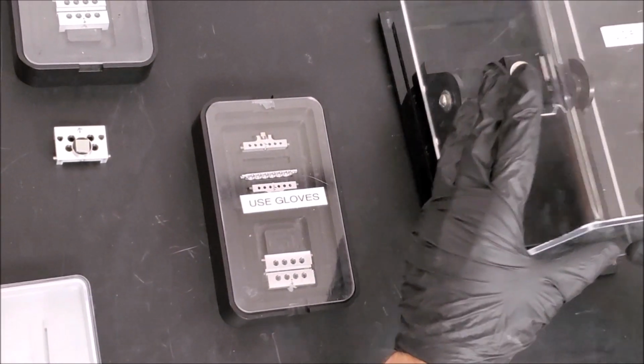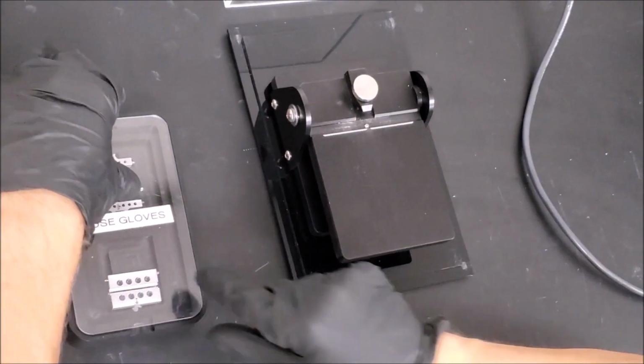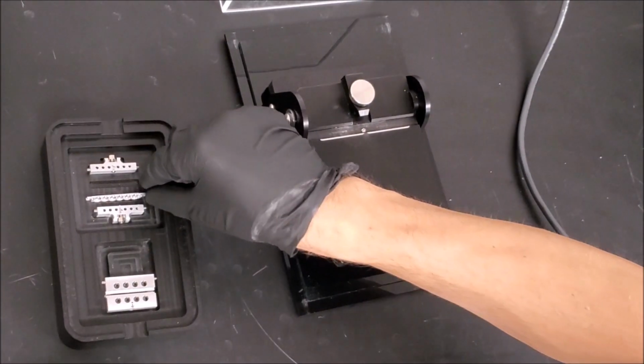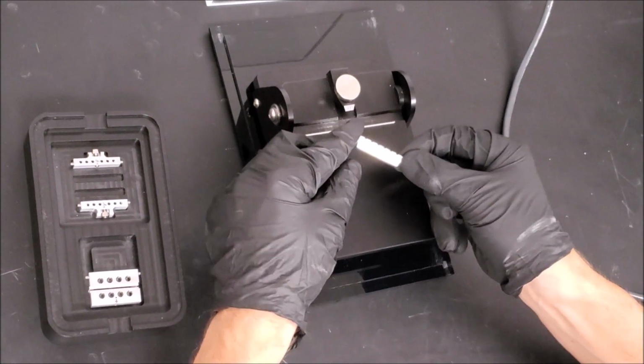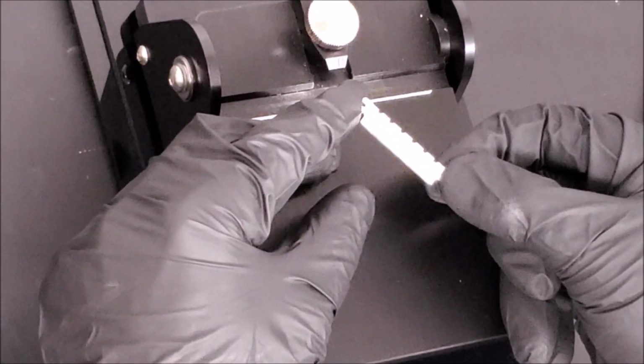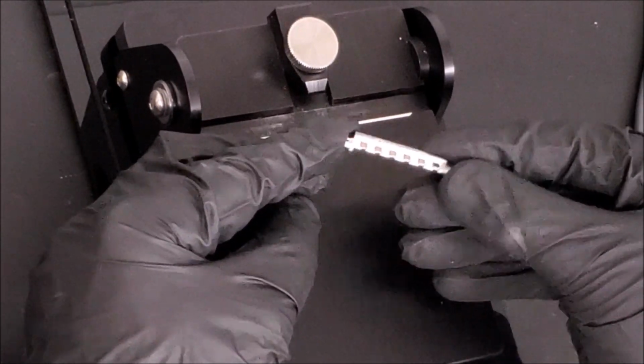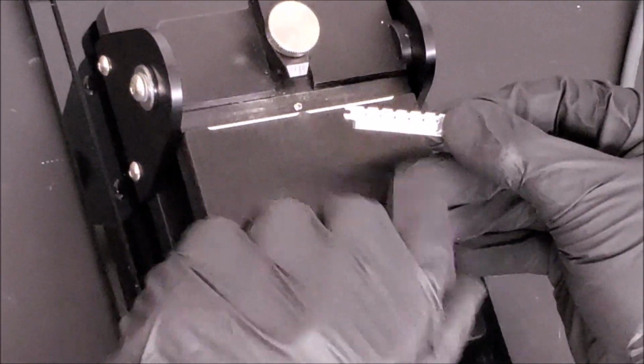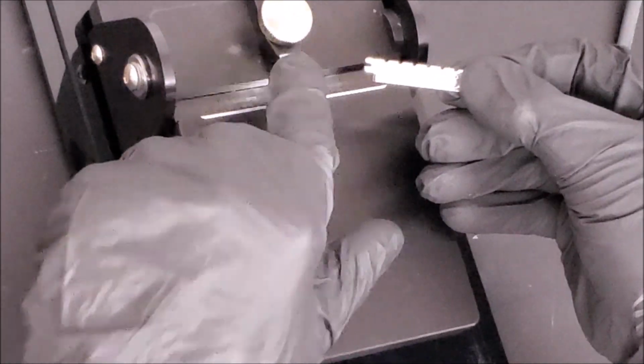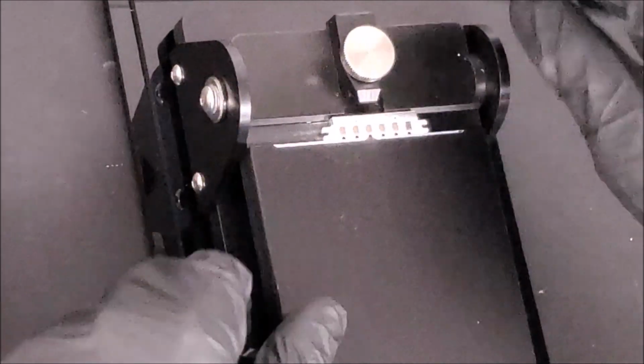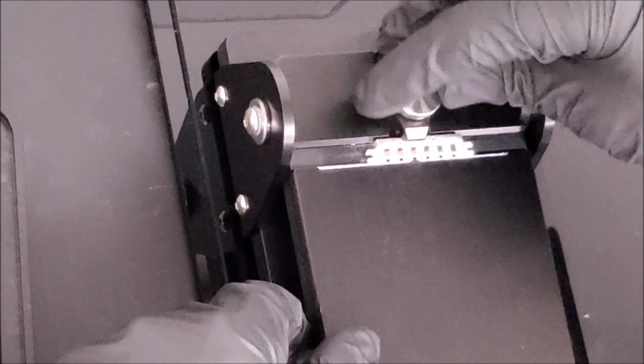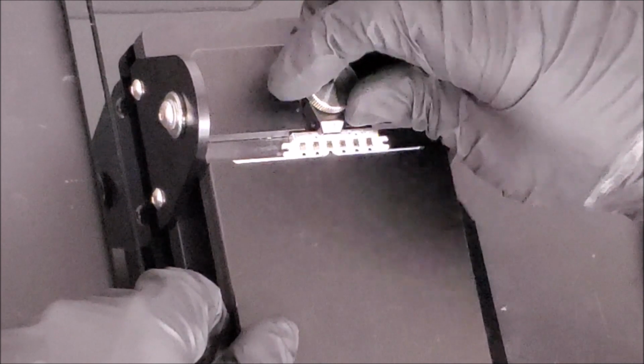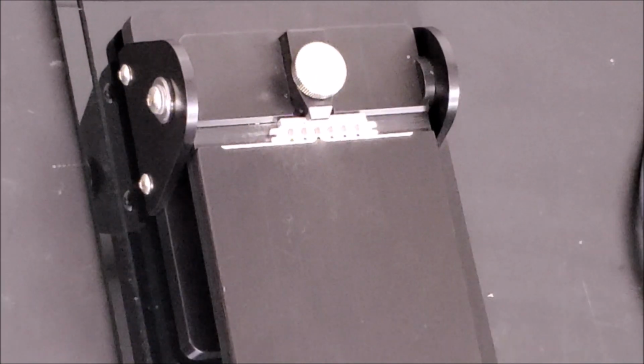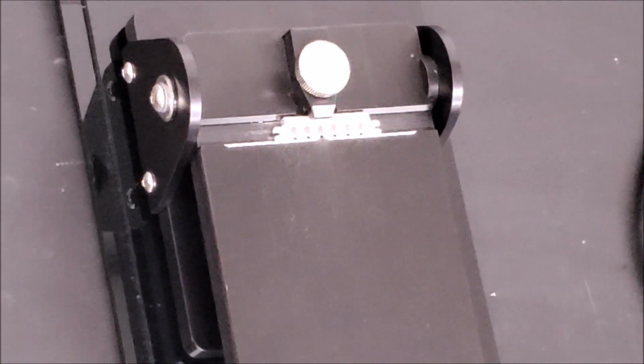To load a grid, uncover the grid loader and then remove the grid holder from its case. Note that the grid holder can accept up to 6 grids. Identify the side of the grid holder with the holes, as this will need to be placed face down into the grid loader. Place the grid holder onto the loader, lining up the pin on the loader with one of the holes on the back of the grid holder. Then tighten down the loader to push up the clip and open up the grid holder to accept a grid.